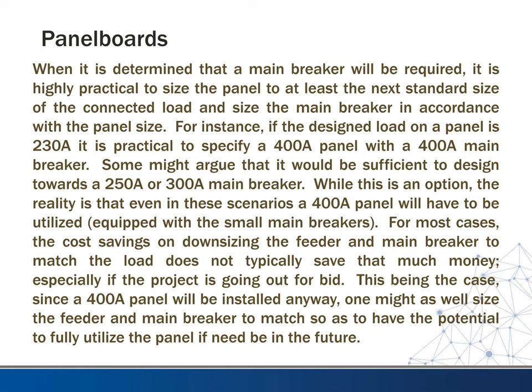Some might argue that it would be sufficient to design towards a 250 amp or 300 amp main breaker. While this is an option, the reality is that even in these scenarios, a 400 amp panel will have to be utilized because there really is no 300 amp panel, and it'll be equipped with a smaller main breaker. For most cases, the cost savings on downsizing the feeder and the main breaker to match the load does not typically save that much money, especially if the project is going out for bid.